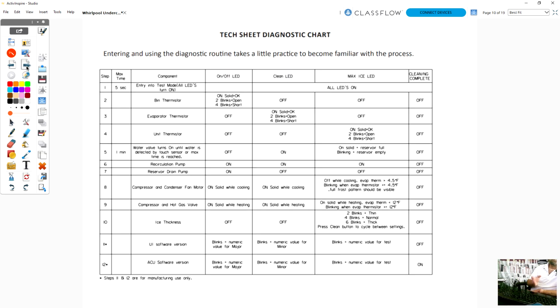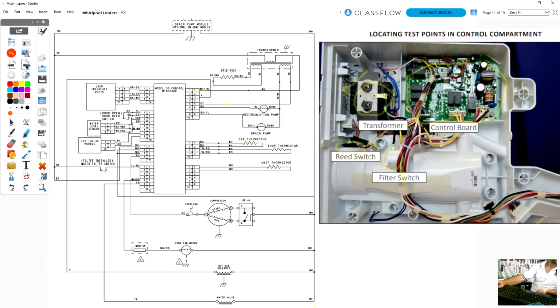So ice removal is hot gas valve, compressor, and that's it. It just blows hot refrigerant into the evaporator and the ice slides off. Ice production is compressor, condenser fan, and recirculation pump. During ice ejection, we have a drain valve and the water valve that are both initiated, but not at the same time. So that is the operation.